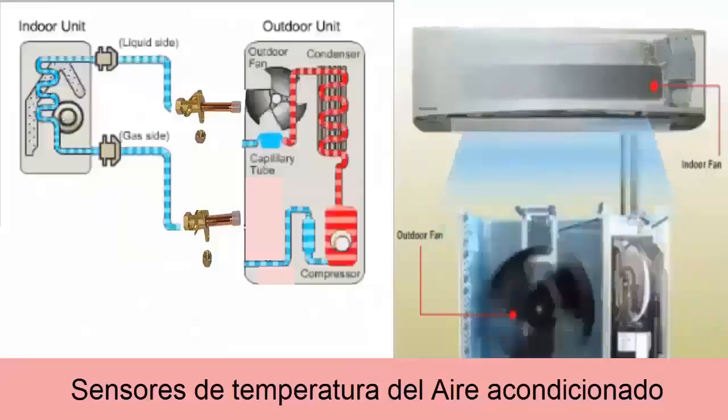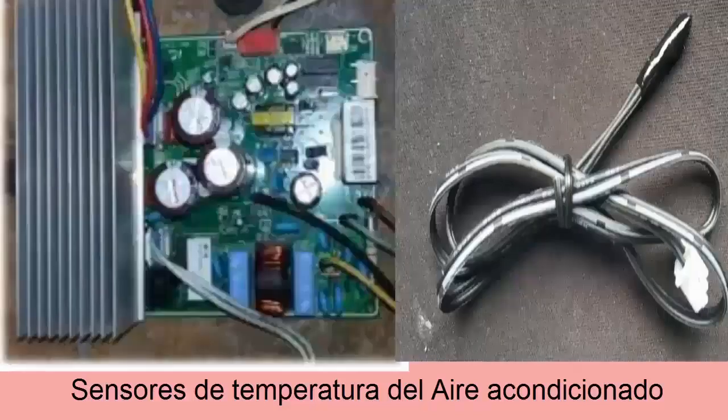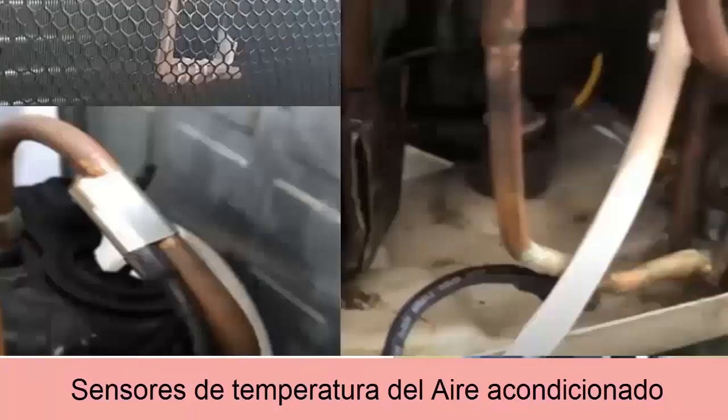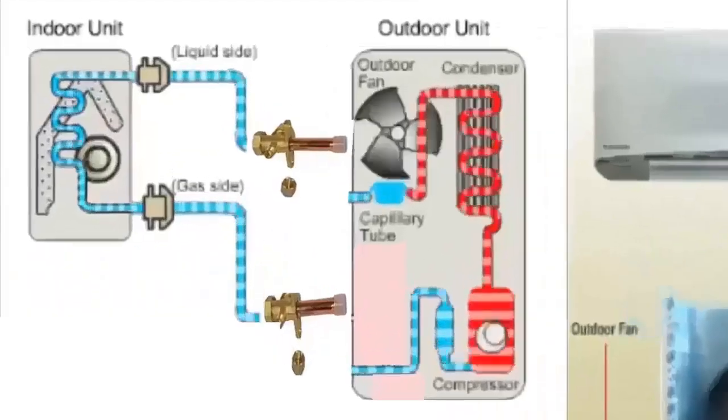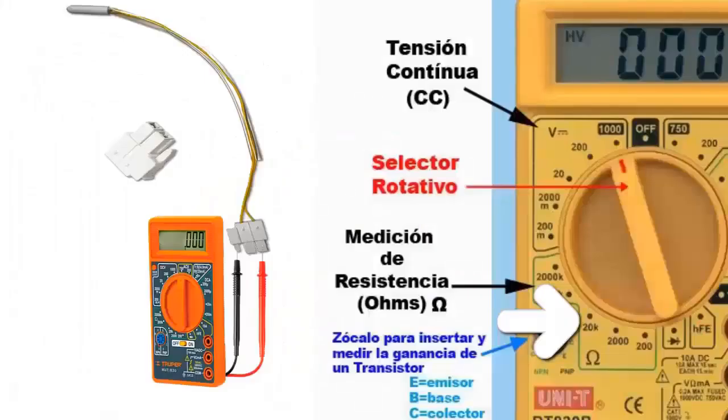Since the diagnostic procedure for any temperature sensor is practically the same, let's look at the following recommendations to address any of the above fault codes. 1. Check the sensor connections. 2. Clean the connections. 3. Confirm the correct position of the sensor.